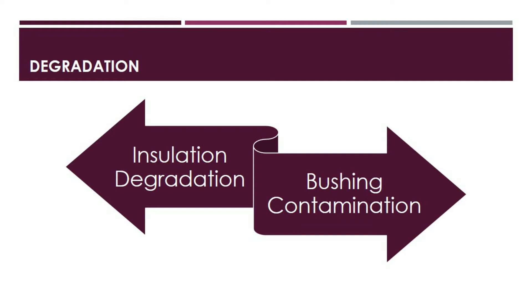Using the procedures given in the ANSI or IEEE Loading Guide, the effects of loading profiles, loading increase, and ambient temperature on the asset's condition, loss of life, and life expectancy can be assessed. The impact of overloading transformers above their nameplate rating on bushings, tap changers, and auxiliary components is discussed in IEEE Standard C57.91, which also includes formulas for calculating the life loss of a transformer unit due to overloading and temperature rise. This standard also establishes an initial baseline for the size of transformer that should be selected to support a certain number and type of consumers.